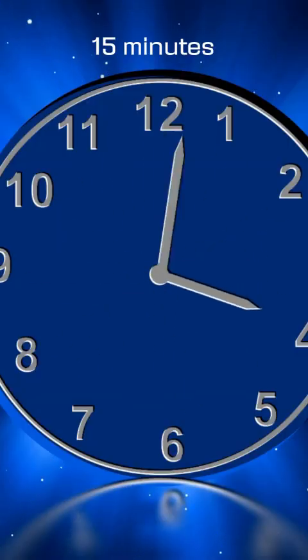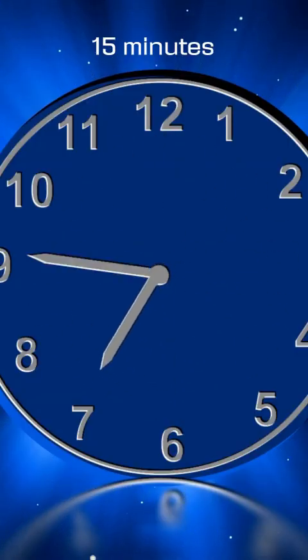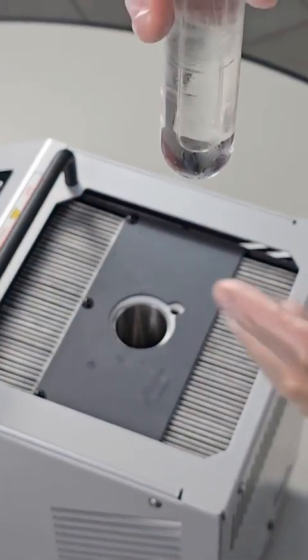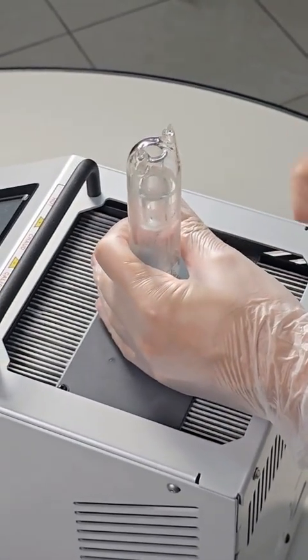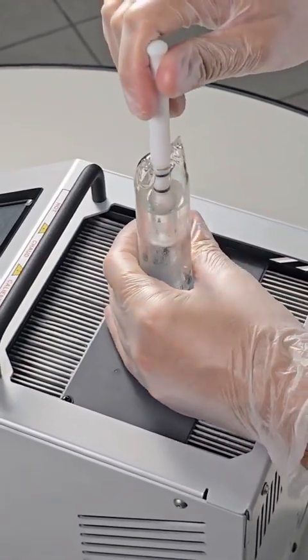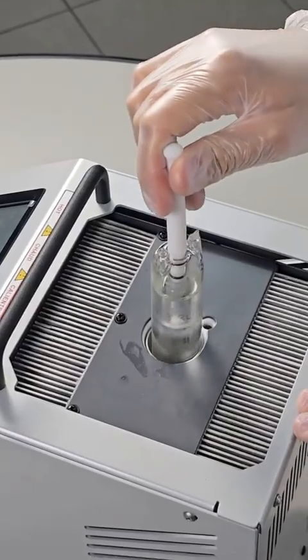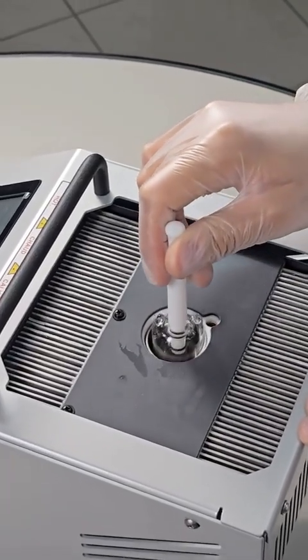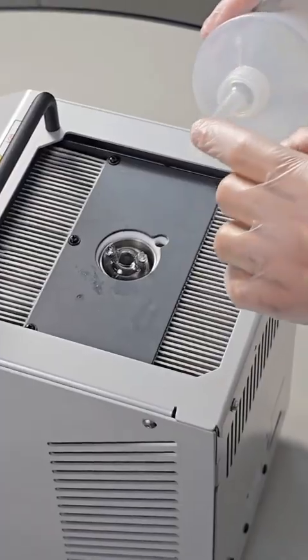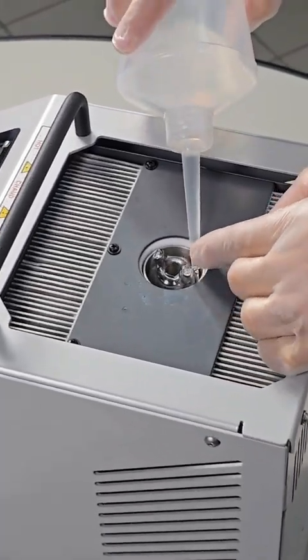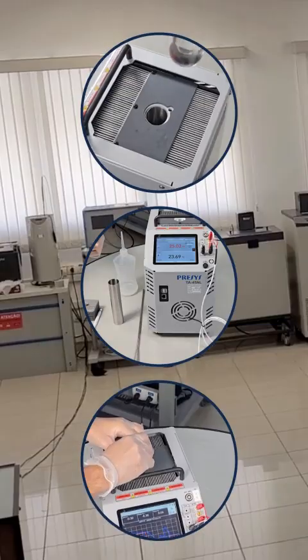It is recommended to wait at least 15 minutes before using the cell for calibrations, allowing the system to reach thermal equilibrium after handling. During use, maintain a heat transfer medium with ethanol in the well and pre-cool the thermometers to be calibrated to avoid accelerated melting of the ice mantle.